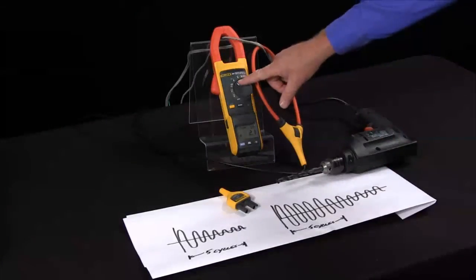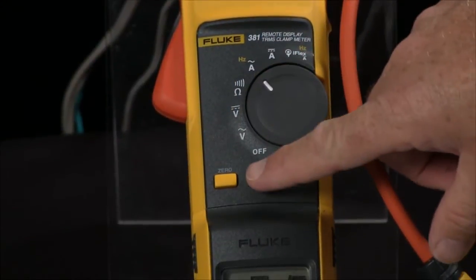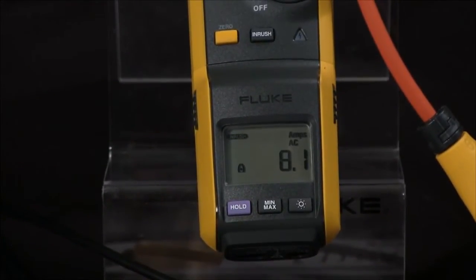what we first do is we turn it to amps and then we press the inrush key. The meter will wait for you to start the motor and we'll be able to capture the inrush current.